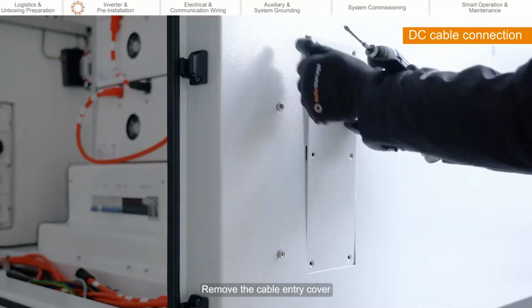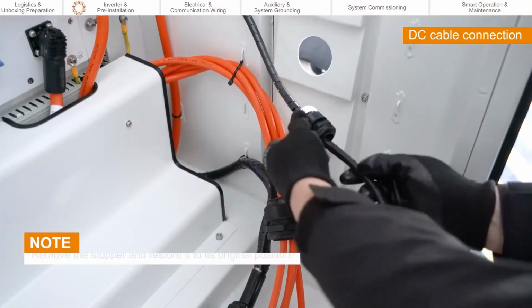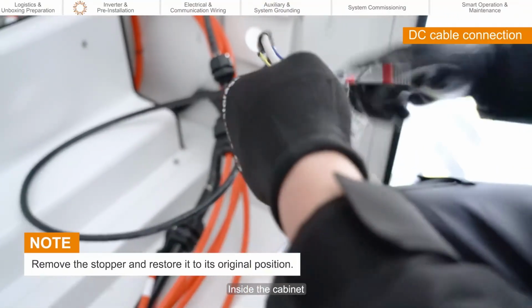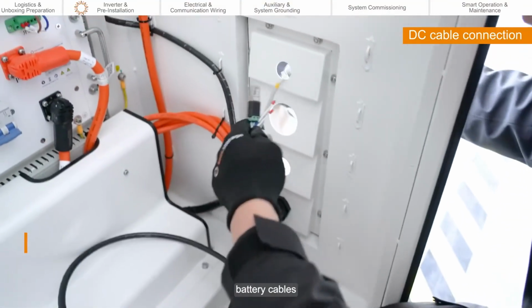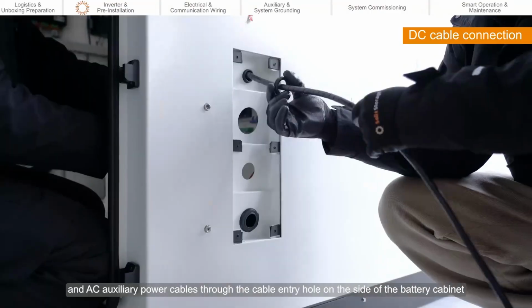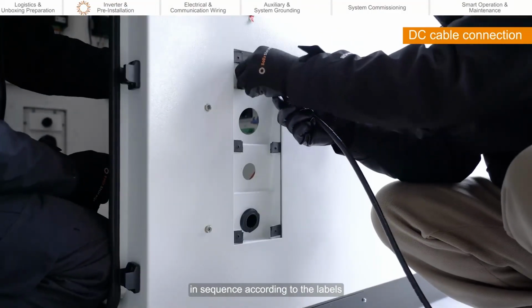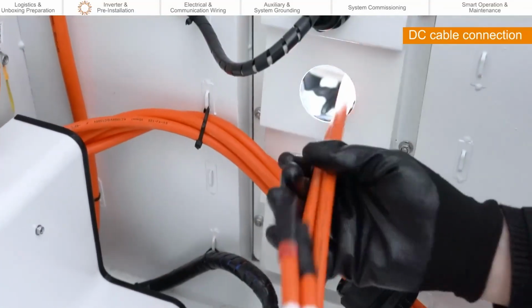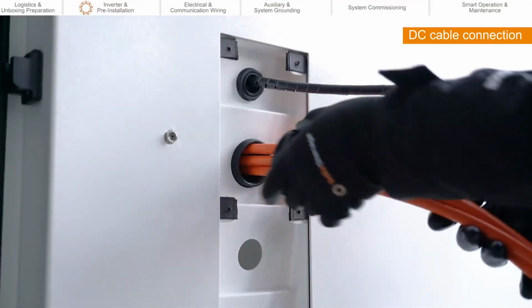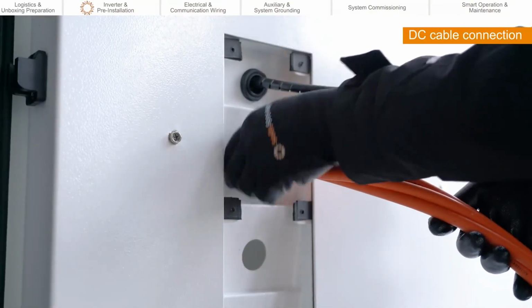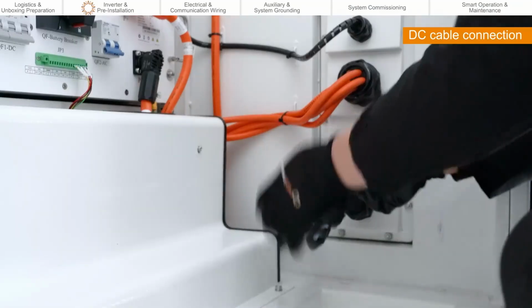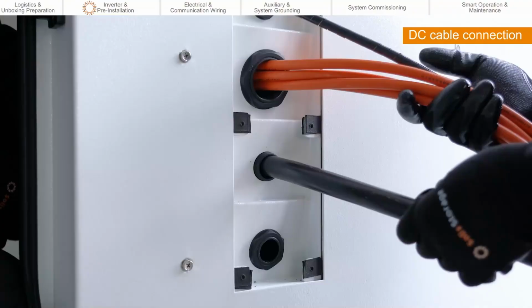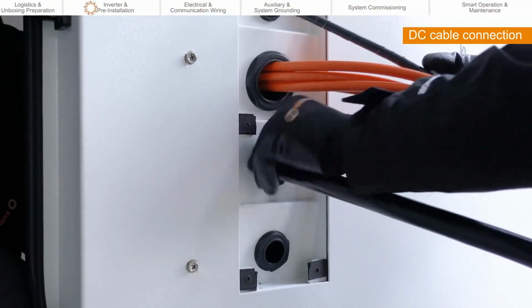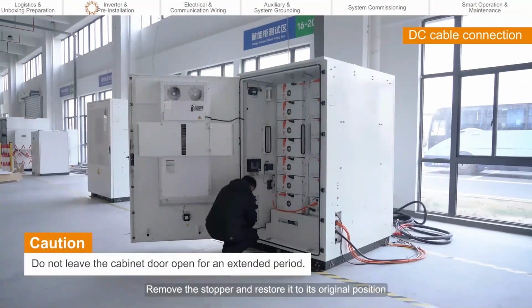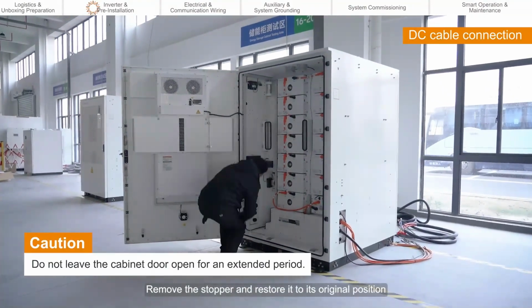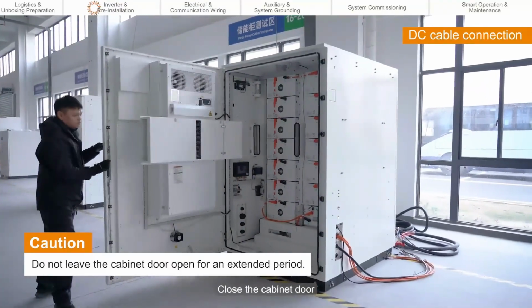Remove the cable entry cover. Inside the cabinet, pass the communication cables, battery cables, and AC auxiliary power cables through the cable entry hole on the side of the battery cabinet in sequence according to the labels. Remove the stopper and restore it to its original position. Close the cabinet door.